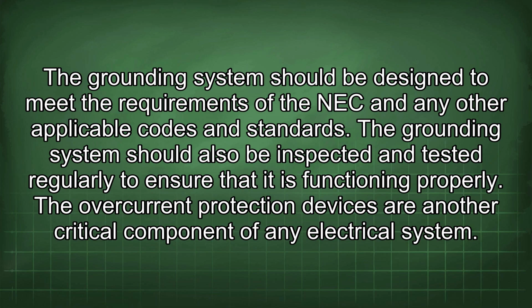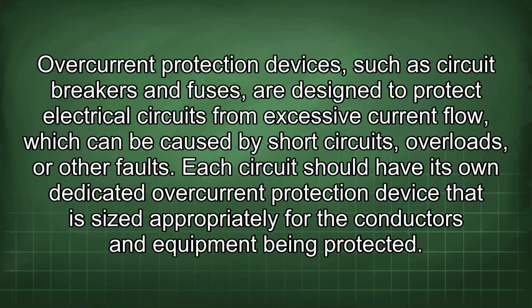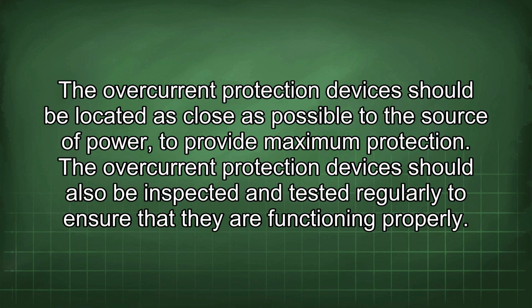The overcurrent protection devices are another critical component of any electrical system. Overcurrent protection devices, such as circuit breakers and fuses, are designed to protect electrical circuits from excessive current flow, which can be caused by short circuits, overloads, or other faults. Each circuit should have its own dedicated overcurrent protection device that is sized appropriately for the conductors and equipment being protected. The overcurrent protection devices should be located as close as possible to the source of power to provide maximum protection. The overcurrent protection devices should also be inspected and tested regularly to ensure that they are functioning properly.